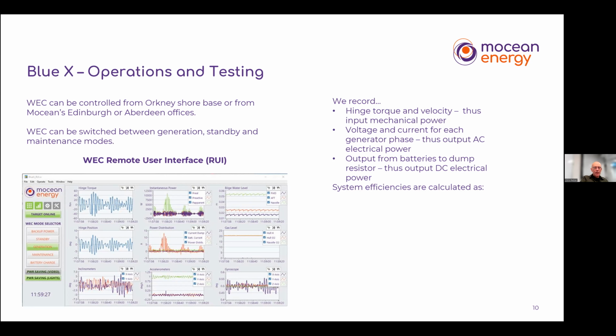Going back to the user interface there, in the middle section, we get the outputs from the generator. So we're measuring voltage and current, and again, the product of those two for each of the phases gives us the output electrical power. And we're rectifying that and dumping it into batteries and storing it. And on demand, we can release that energy into a dump resistor, burn it off, and measure the amount of DC electrical power that we're producing. And we can calculate those efficiencies. We can calculate the electrical and mechanical efficiencies by comparing those readings, comparing those values.